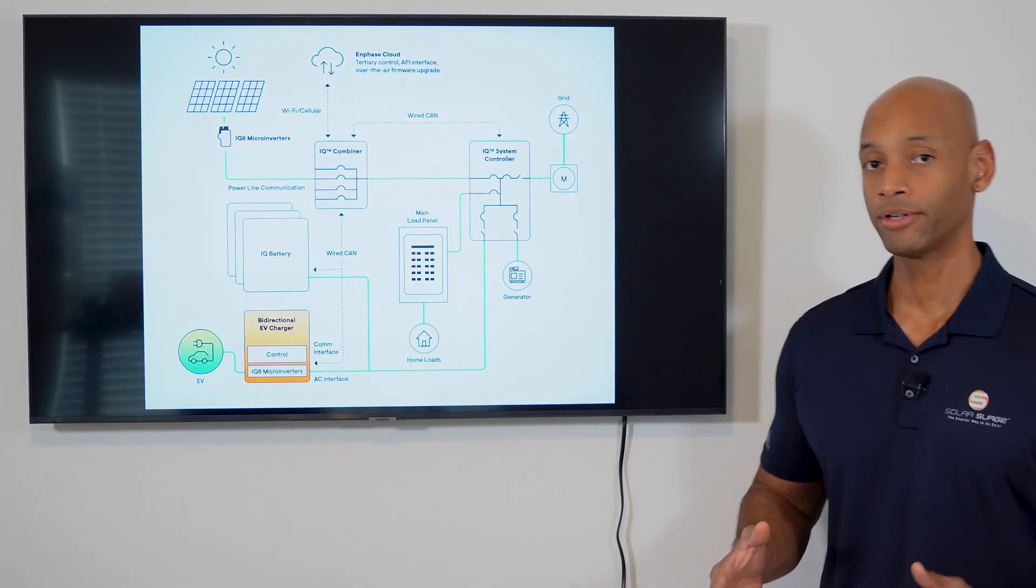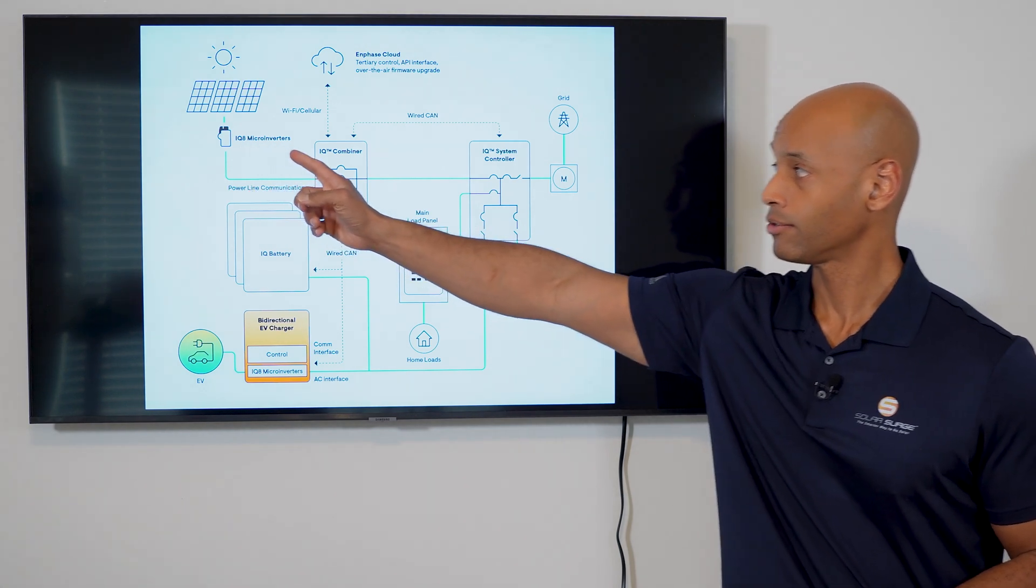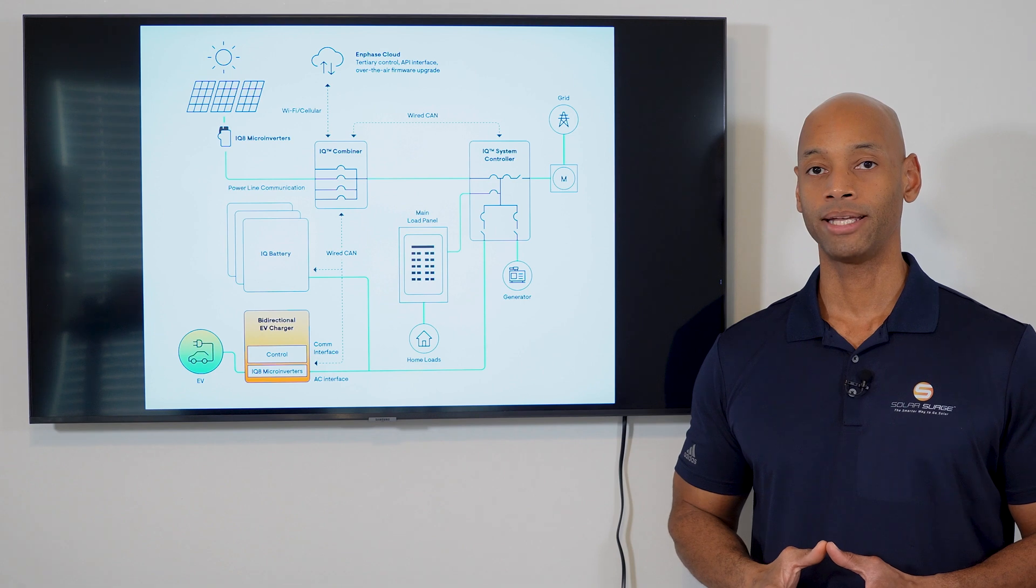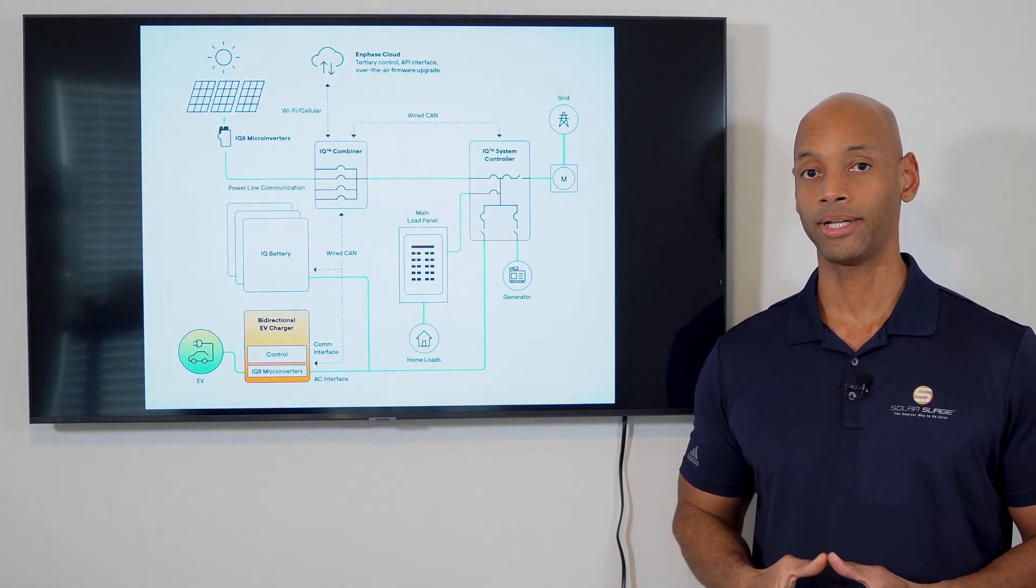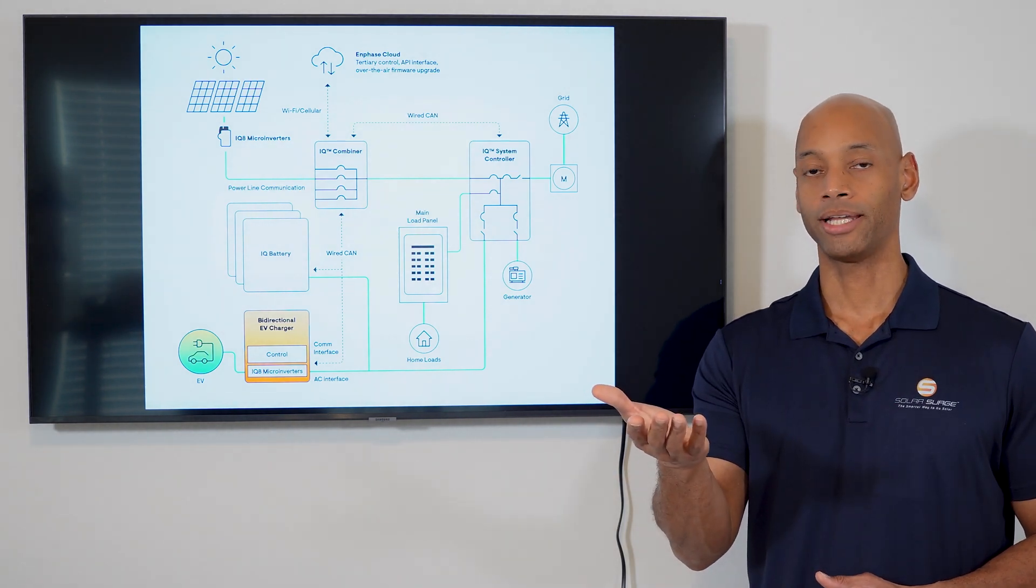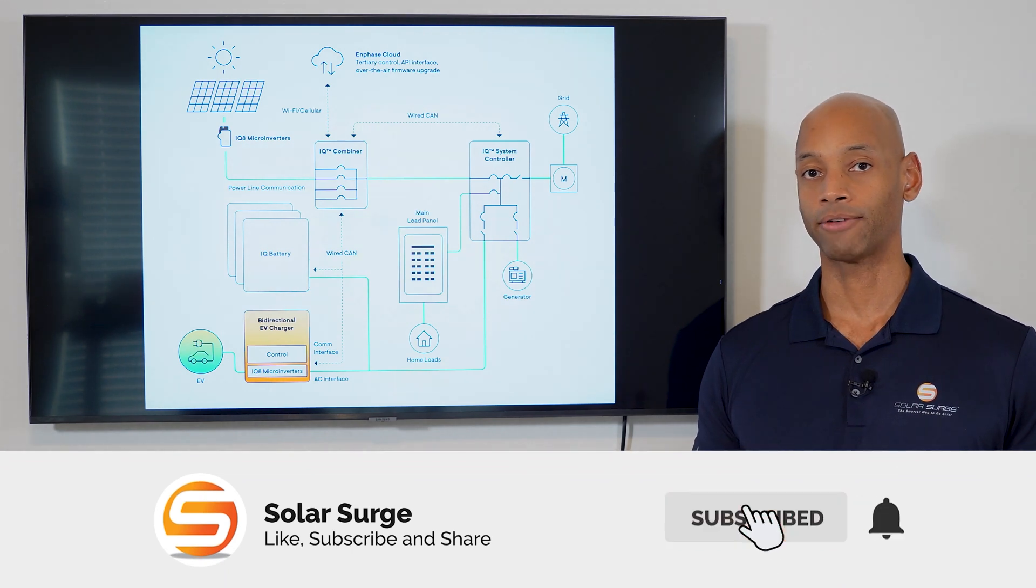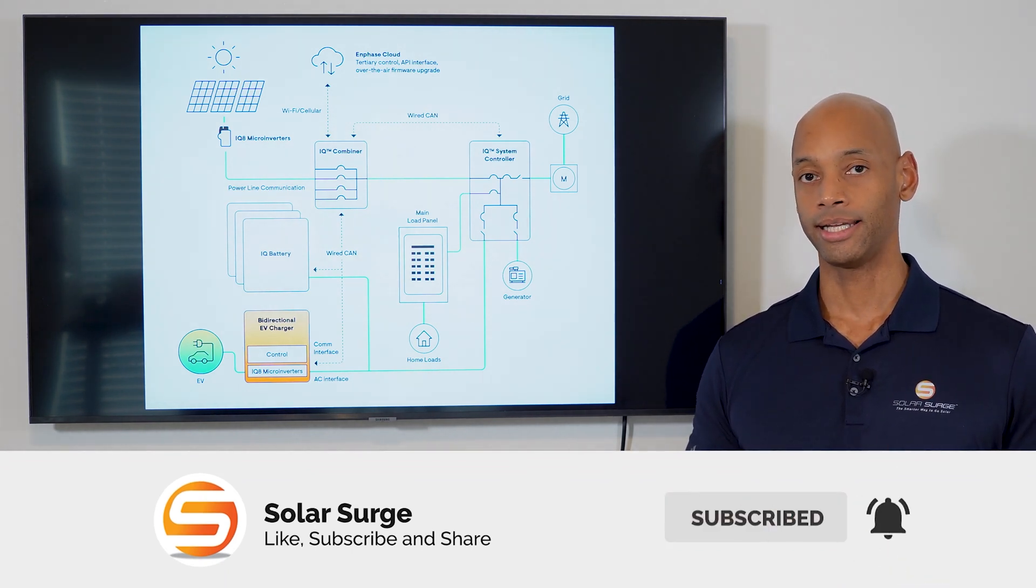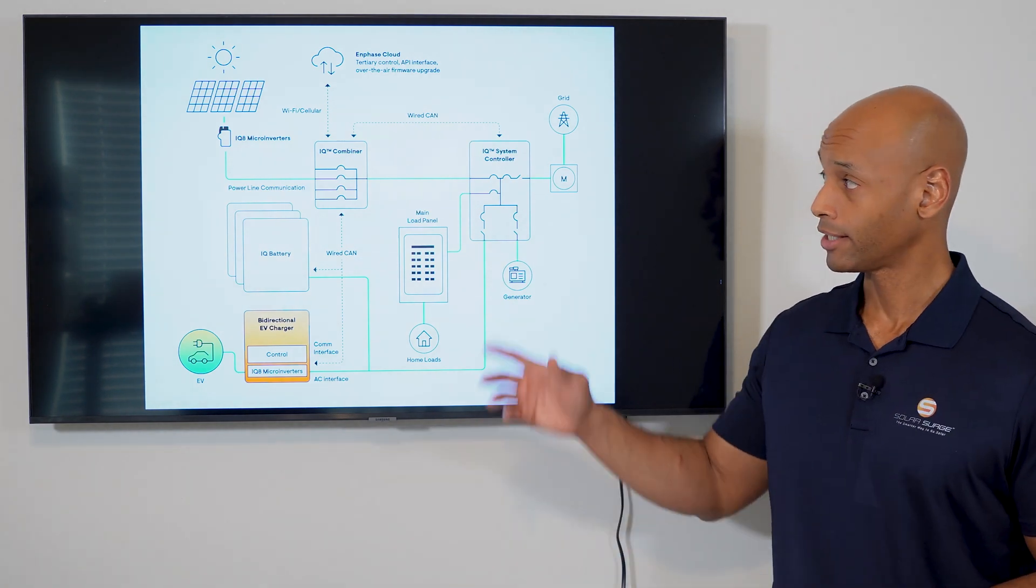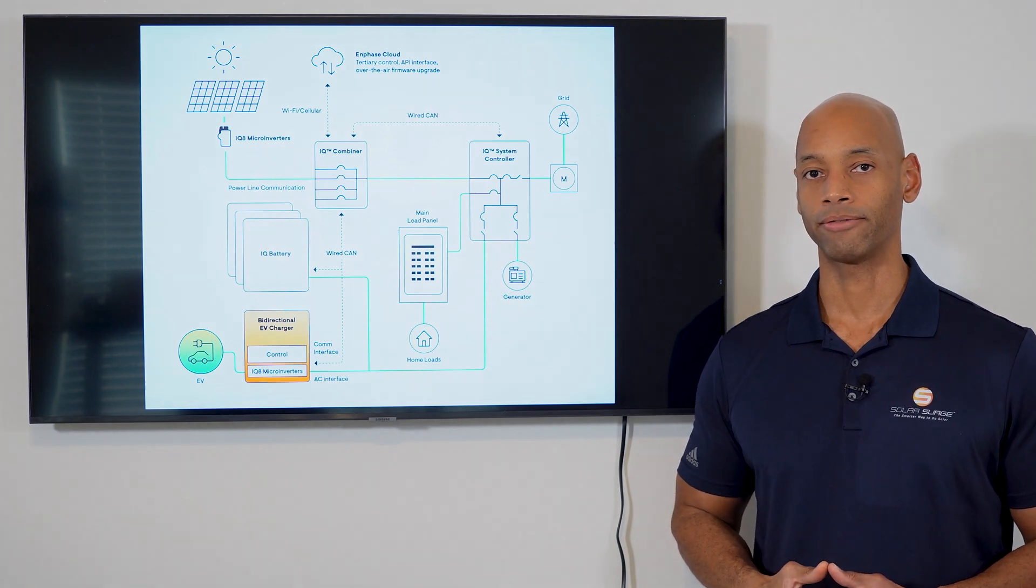It's the inverter system that does this function, and with Enphase they use what's called microinverters. What a microinverter means is that each solar panel has its own inverter device - a small device that installs underneath each solar panel. Instead of having one central unit at ground level that does DC to AC conversion for the entire system, with the Enphase architecture each individual solar panel has its own microinverter.